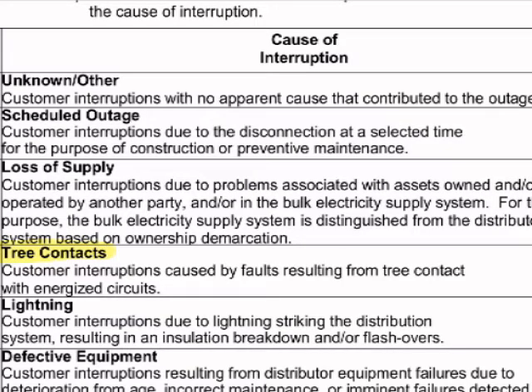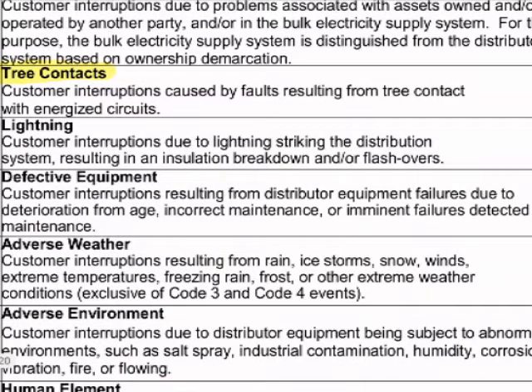Tree contacts is the first of our cause codes that's generally going to be resulting in a fault. This comes down when you get a branch or an entire tree comes crashing down into your lines, gets tangled up in it, and this is going to result in a flow of electricity either through the tree or conductor to conductor, depending how things sag when they fall. That's going to create an electrical fault that will result in an outage. And tree contacts are generally mitigated by tree trimming. Utilities run a trimming program to keep the trees well back of the lines. The standard is generally 10 feet. And as long as the trees are far enough back, they tend not to get into the lines, and you can mitigate the number of tree contacts that you have.